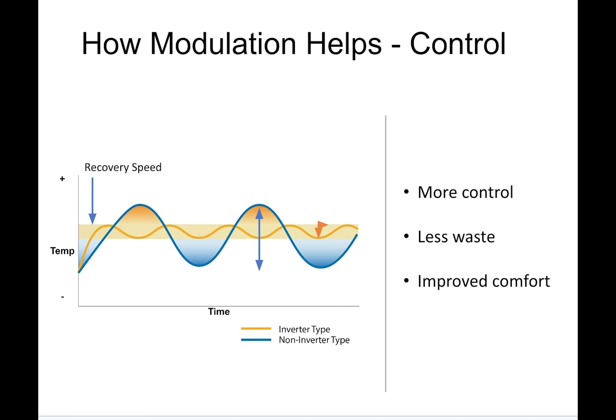Old school heat pumps, on the other hand, have constant speed compressors and fans and some may even have a capillary tube rather than an expansion valve for the metering device. These older heat pumps are primarily controlled by sensing the refrigerant pressure and then turning the compressor on and off based on a fixed set pressure, resulting in operation that crudely approximates the thermal loads of the home — analogous to driving an automobile and slamming on the brakes and then slamming on the gas pedal.